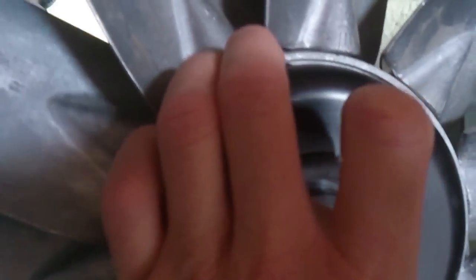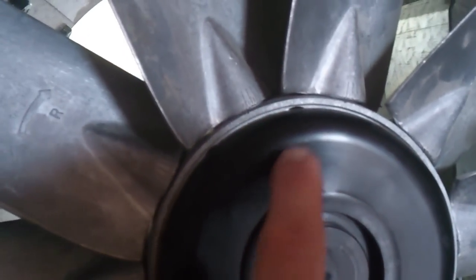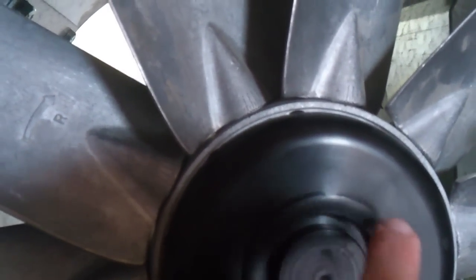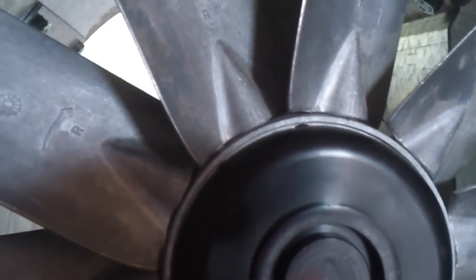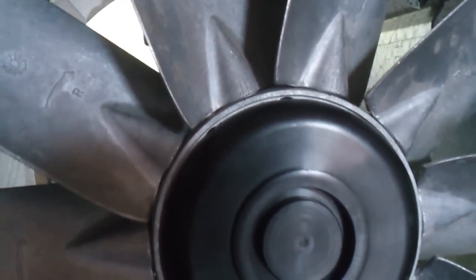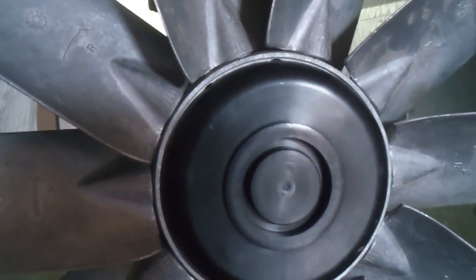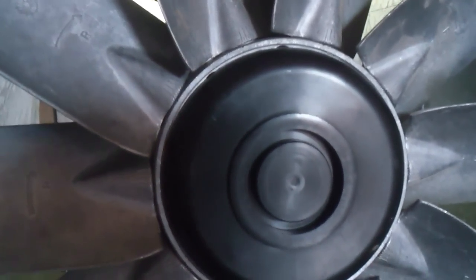This is the cover. I couldn't remove the cover. If I could, you would see the nuts holding all those blades on the impeller. If you look closer here, you can see the gap between the impeller and the casing. That's the gap I talked about once. The bigger that gap is, the less efficient your fan is.